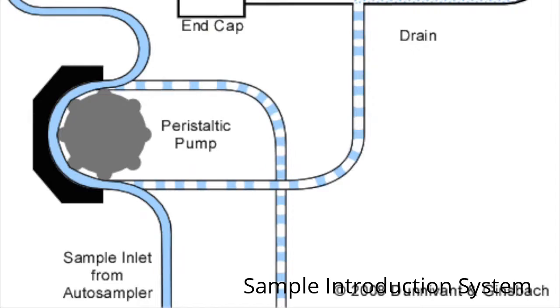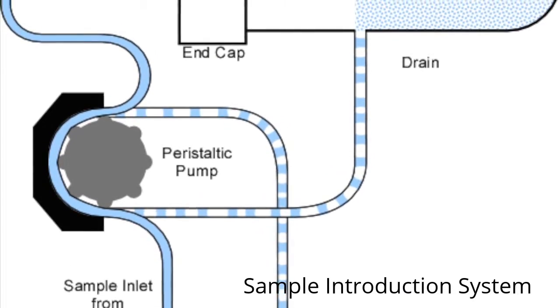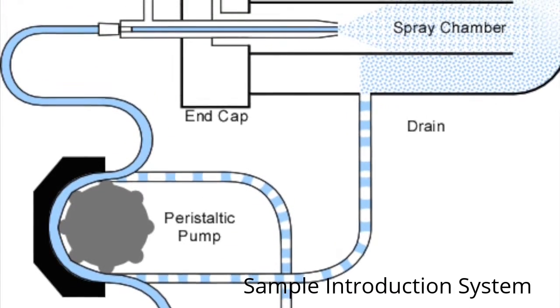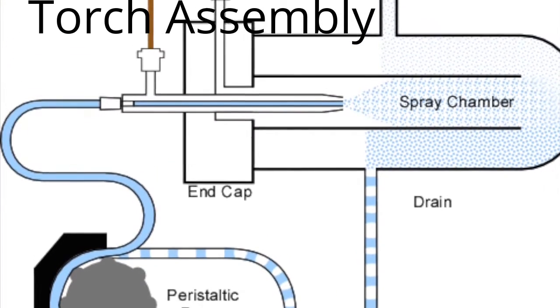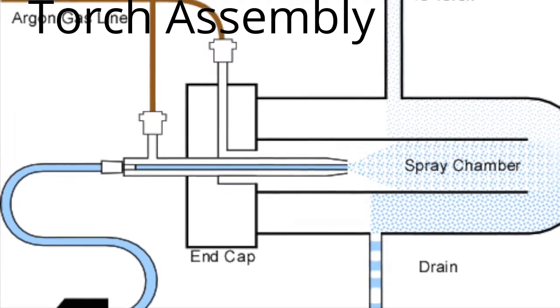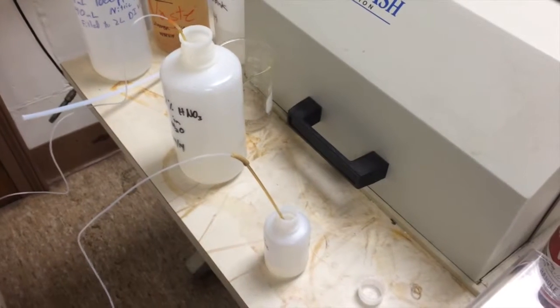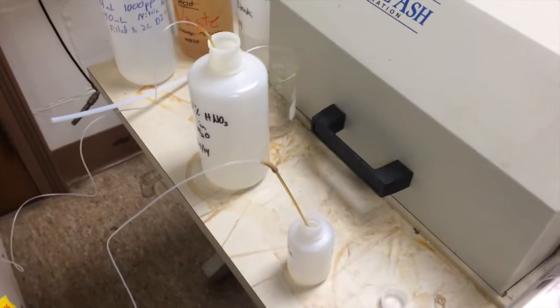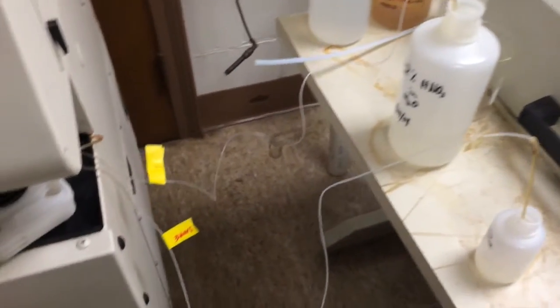Your water sample begins its journey in a part of the instrument known as the sample introduction system. It gets the water sample to the second part, called the torch assembly. The pump continuously takes up small amounts of the water sample through small tubes into something called the nebulizer.